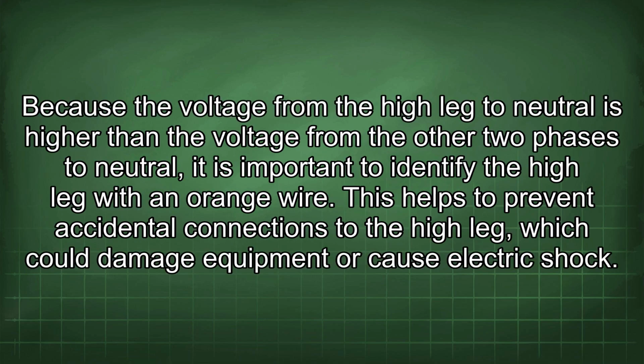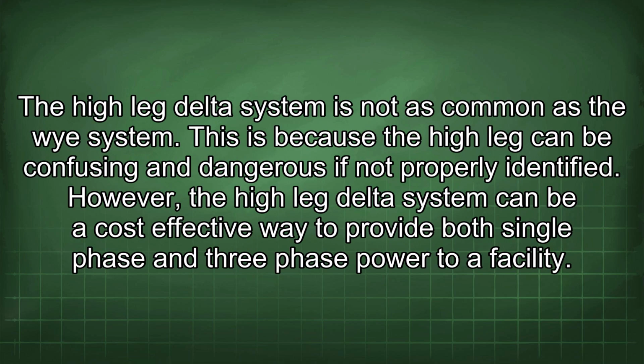Because the voltage from the high leg to neutral is higher than the voltage from the other two phases to neutral, it is important to identify the high leg with an orange wire. This helps to prevent accidental connections to the high leg, which could damage equipment or cause electric shock. The high leg delta system is not as common as the Y system. This is because the high leg can be confusing and dangerous if not properly identified. However, a high leg delta system can be a cost-effective way to provide both single-phase and three-phase power to a facility.